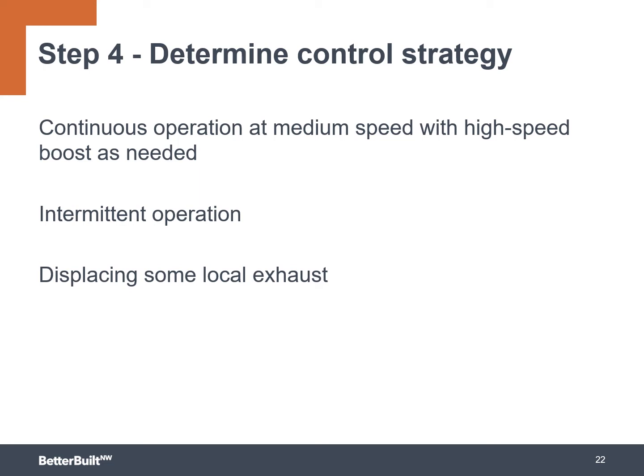So there may be a little bit of cost savings there by combining the continuous ventilation from the heat recovery ventilator, that continuous exhaust, with the on-demand local exhaust, so that at any point in time, you're either constantly moving a small amount of air, or when combining the two, taking care of any local instances creating moisture or pollutants, and removing them effectively at that time.